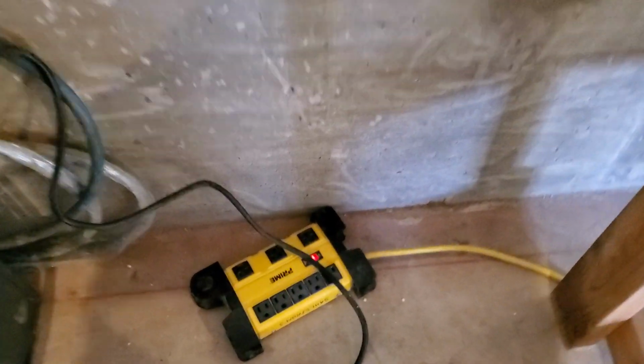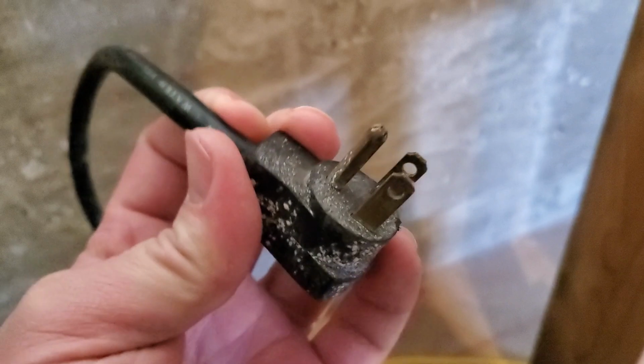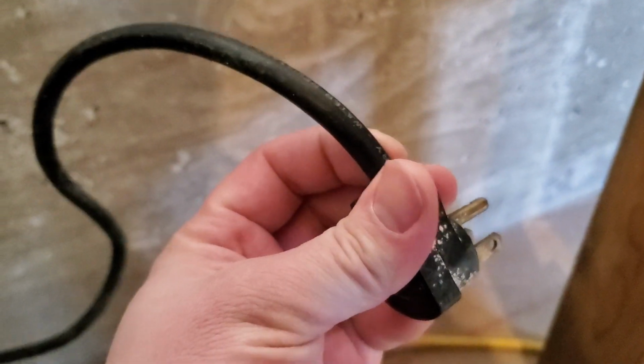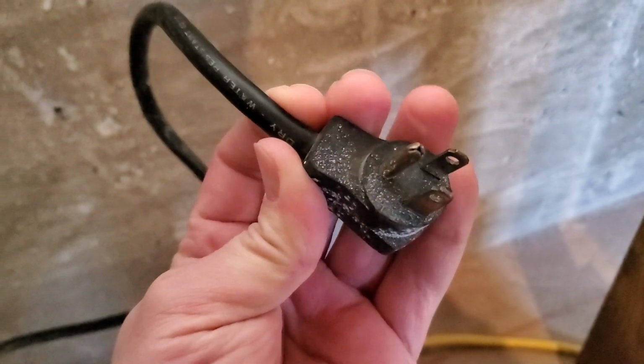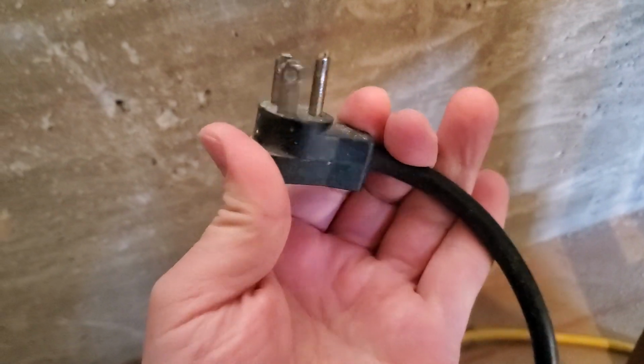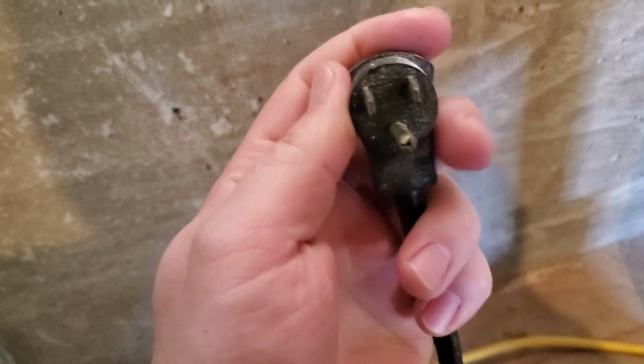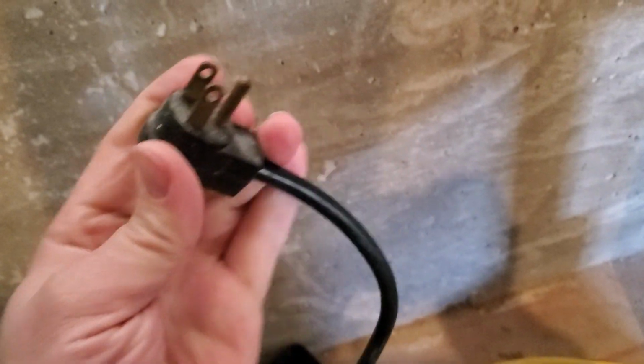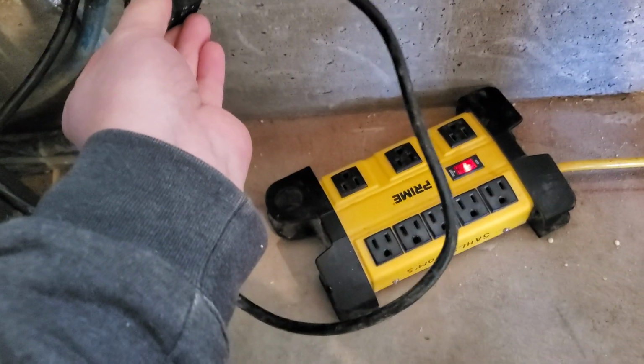Okay, so for wiring the furnace, you're going to need a drop cord of some kind, and furnaces typically require a 15 amp 110 volt circuit, which means you could use a 14 gauge drop cord. So use a drop cord and then make sure that you have your ground prong. I'll show you what those connections look like inside of the furnace here where this connects.